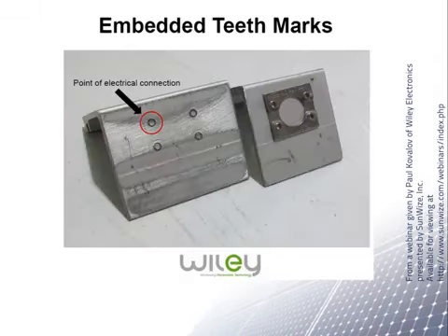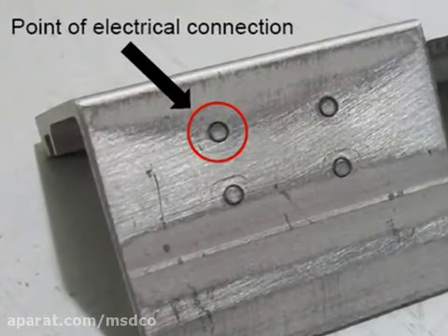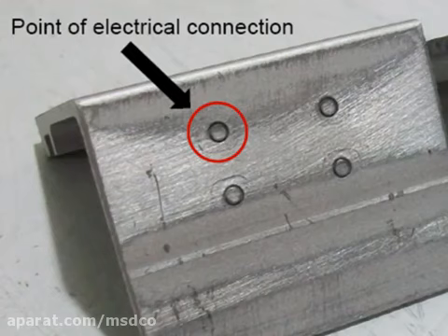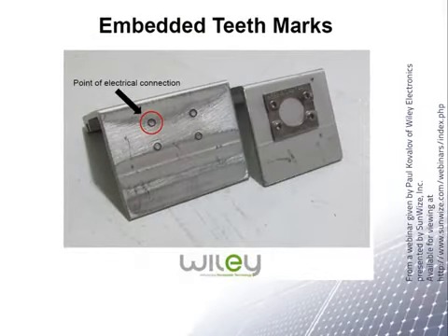This picture shows the teeth marks that a WEEB connector makes in a piece of aluminum. Because the teeth dig in this way, you are not supposed to use a WEEB connector more than once. If, for some reason, you need to remove a PV module, you are supposed to use a new WEEB connector when you return or replace the module.